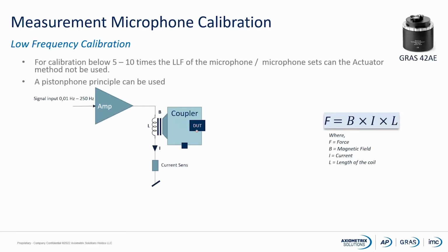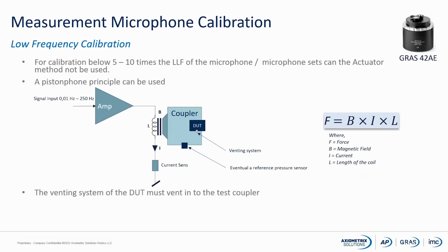The force is equal to the pressure the speaker is able to give us inside our coupler. If we measure the current, then we can also get an idea of what the force or the pressure is inside the little chamber. That's the principle in a chamber like this. When we are doing low frequency calibration, it's very important that the venting system of the microphone is venting into the whole coupler, because otherwise we will just measure the difference between the pressure inside the coupler and the pressure outside the coupler, and that's not the idea.